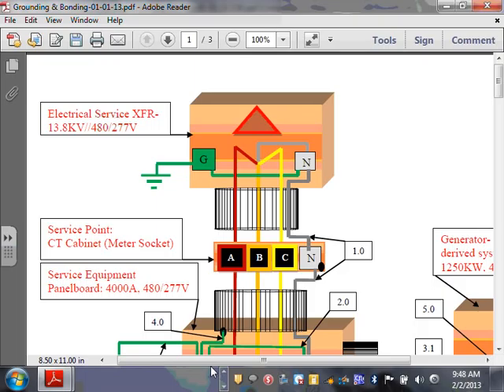So what's wrong with this? Nothing wrong, except when you try to terminate a transformer rated for 3,000 amp to a switchgear that's rated for 4,000 amp, they don't match, not enough lugs. So we came up with that termination box, right? Am I right on that? Everybody had this experience before? So that's how the termination box came to be.